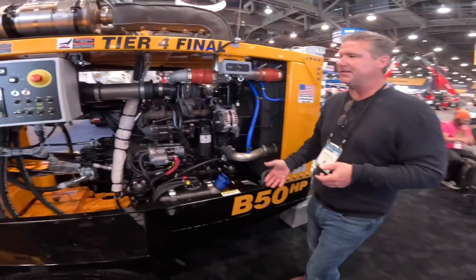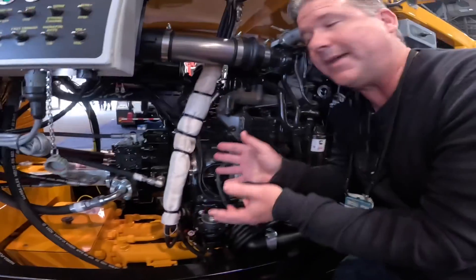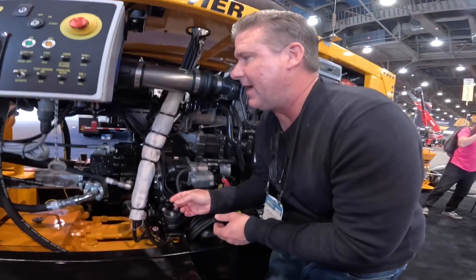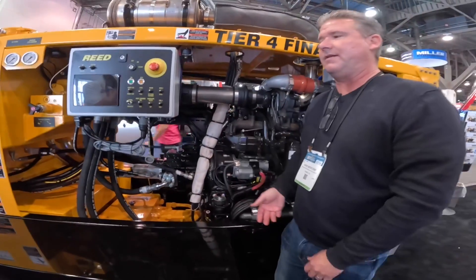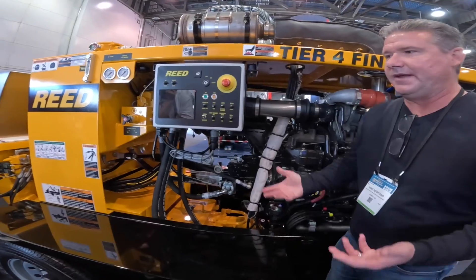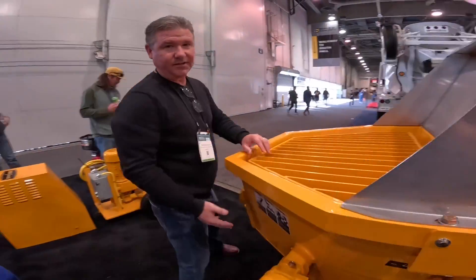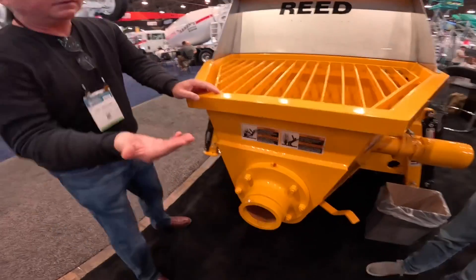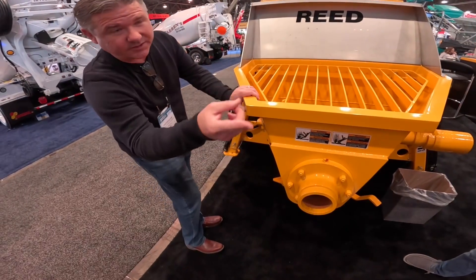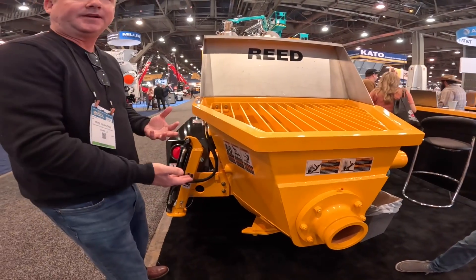It's a 130-horsepower Cummins. This is a different hydraulic system than the C50 SS — it's open-loop, which is more traditional for most line pumps, a simpler machine. We've had the same flat pack since the 80s. Because this one only has 1,361 PSI versus the C50's 2,000 PSI, the C50 has significantly more reinforcement, but this one still doesn't flex.